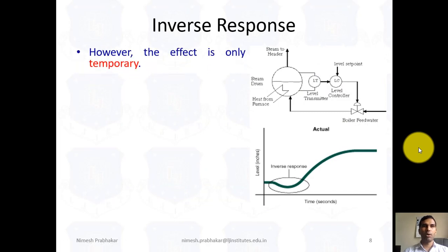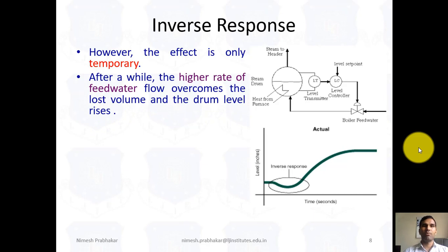However, the effect is only temporary. After a while, a higher rate of feed water flow overcomes the lost volume and the drum level rises. Then after some time it comes to the original position. That means this inverse effect lasts only a temporary time.